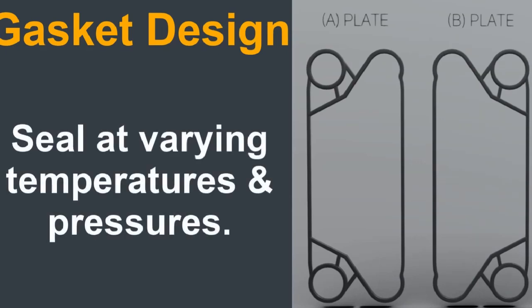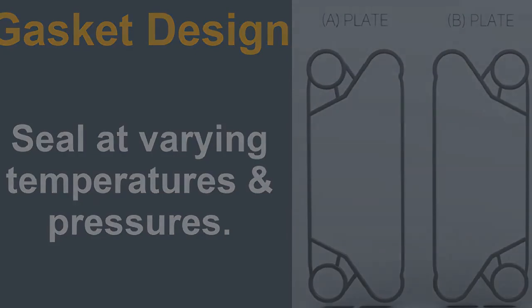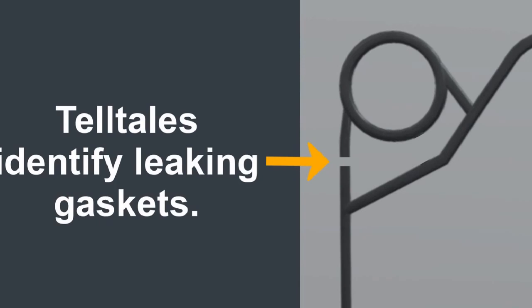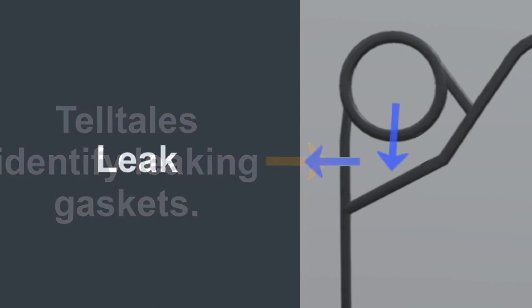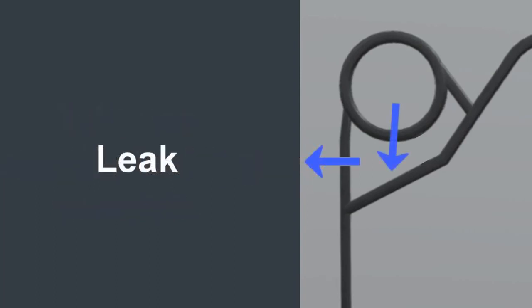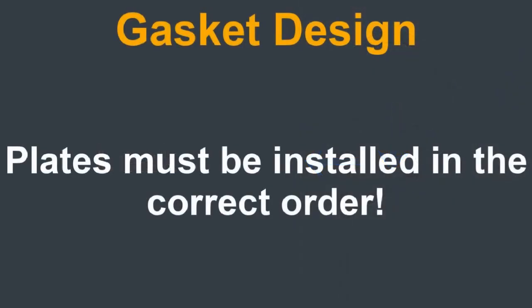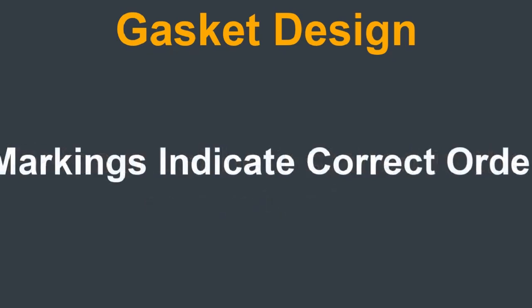Holes in each gasket, known as telltales, are used to identify leaking gaskets. This feature allows operators to change the affected plate before the leaking medium leaks through the next gasket and contaminates the other flowing medium. Because the gaskets guide flow through the heat exchanger, it is essential that they be installed in the correct order. For this reason, gaskets are often fitted with markings so that operators can check each plate is installed in the correct order throughout the entire plate stack.